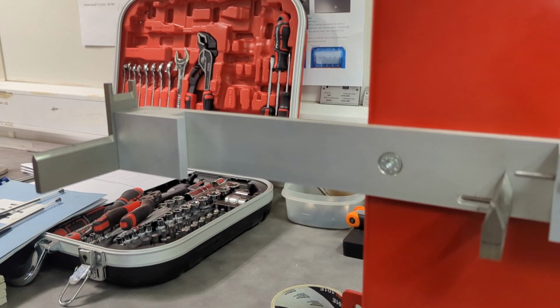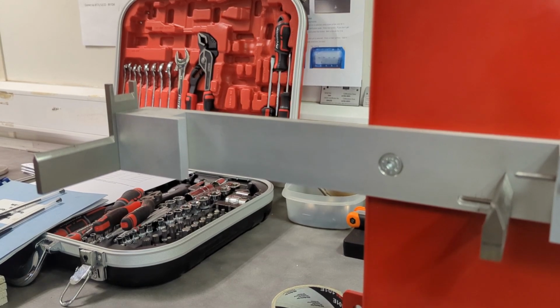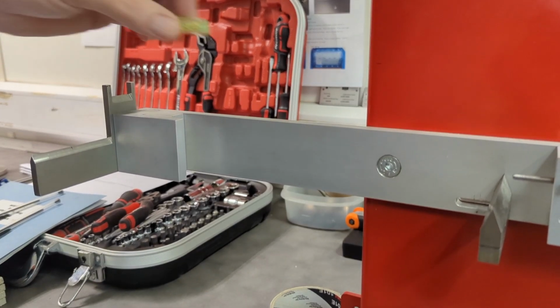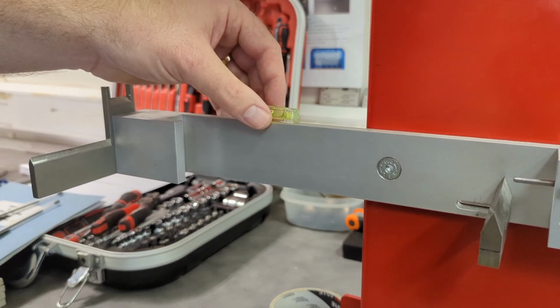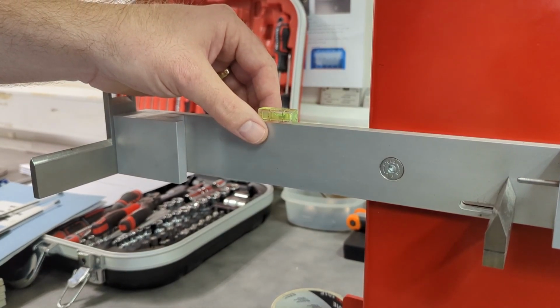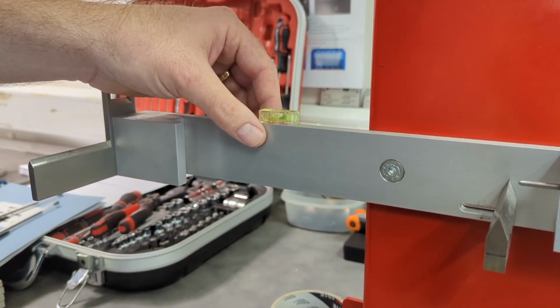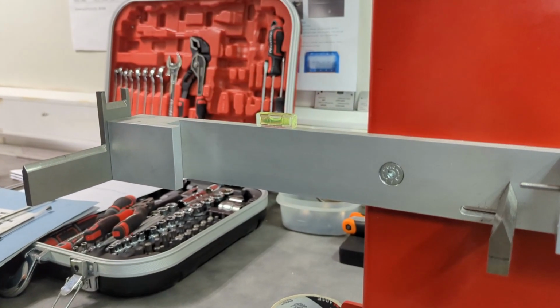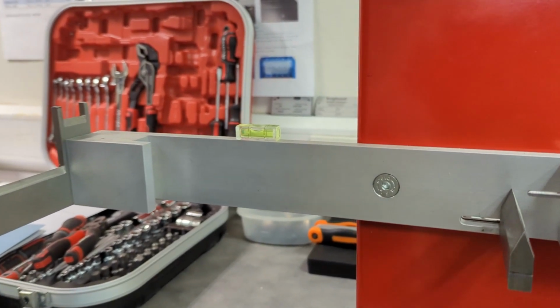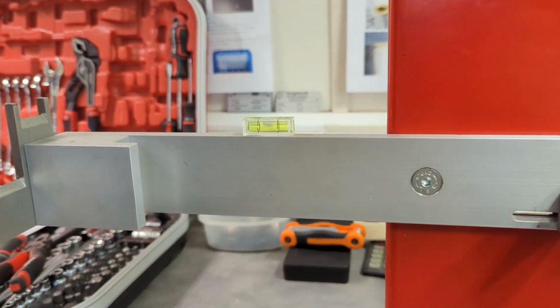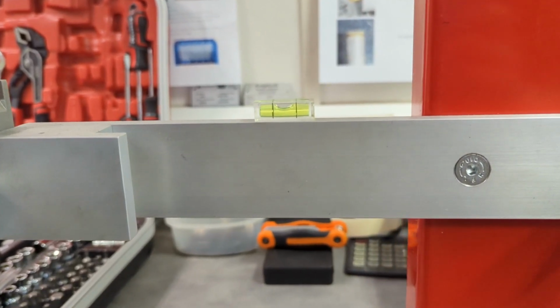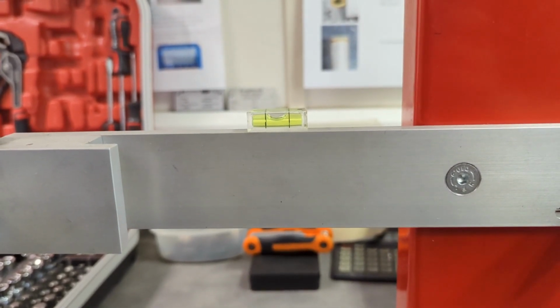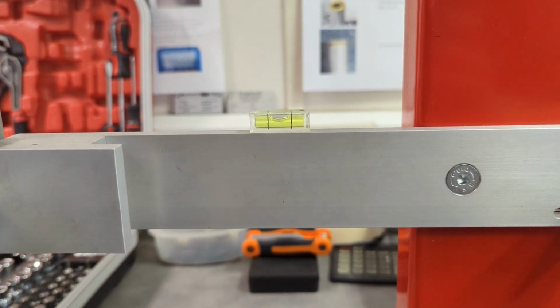It is important that when mounting the calibration jig, either on a desk or on the wall, that the jig is perfectly levelled. Failure to properly level and secure the jig will mean that measurements taken from it will be incorrect. Because of this, it is recommended that you recheck the level of the jig regularly with a high quality level, rather than the level used here for demonstration purposes.